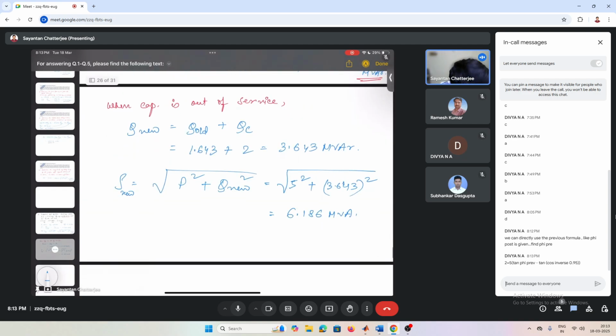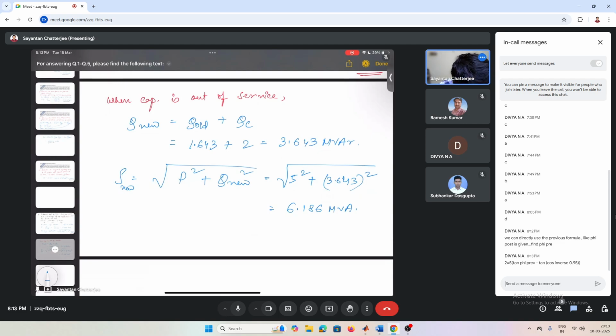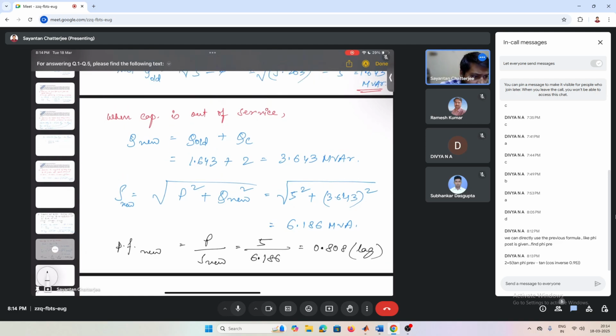So this is the new MVA when the capacitor is out of service. So new power factor will be P is fixed, but S becomes new, so 5 divided by 6.186, that becomes 0.808 lagging. Is it okay? Yes, we can directly use that.